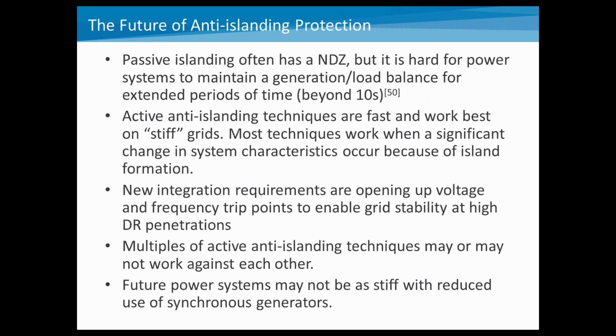So let's move on here. We're getting close to the end, and I'll talk a little bit about the future of anti-islanding protection. Here are some generalized conclusions based on the presentation. Passive anti-islanding techniques often have a non-detect zone. So they definitely have some level of stable voltage and current, or voltage and frequency, which stays inside a normal area, and it's hard to detect inside that specific space. But it's also hard for power systems to maintain that generation load balance for extended periods of time, depending on the control strategies of the distributed generation.